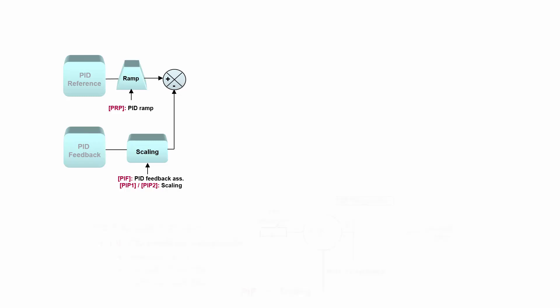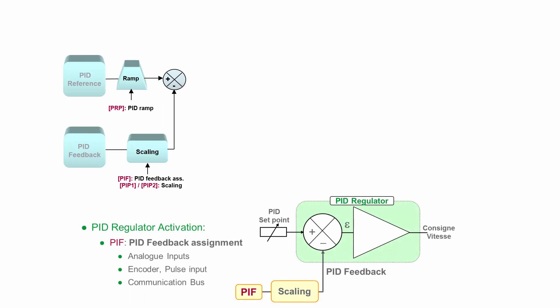Now the first question is how to activate PID regulator. PID regulator in the drive is automatically activated when you assign a PID feedback. One important thing to say: PID regulator inside the drive can only work with variable speed drive.